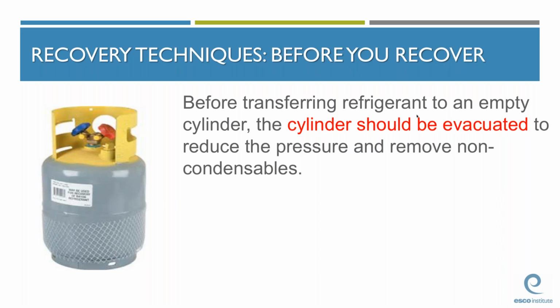Another note on recovery: before transferring refrigerant to an empty DOT-approved refrigeration or recovery cylinder, make certain that your students evacuate the cylinder to reduce its pressure and remove non-condensables. Otherwise, good refrigerant can become contaminated if it's transferred into a recovery cylinder that has not been properly evacuated. So it's super, super important that we stress that with our students to avoid contaminating good refrigerant.